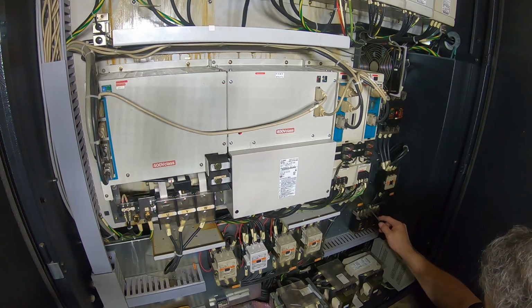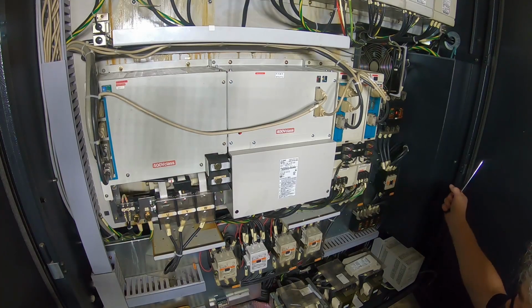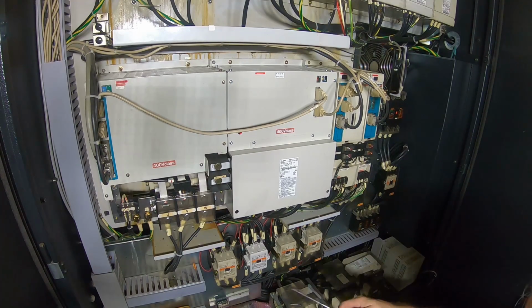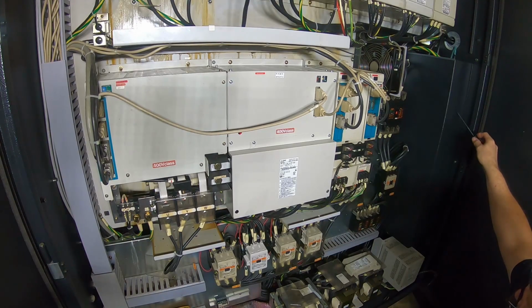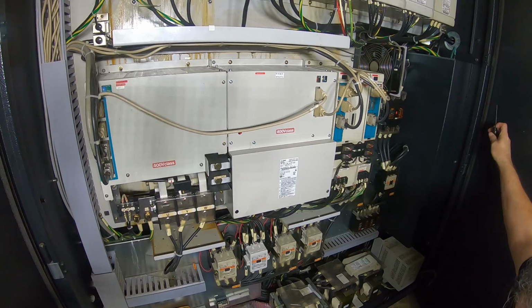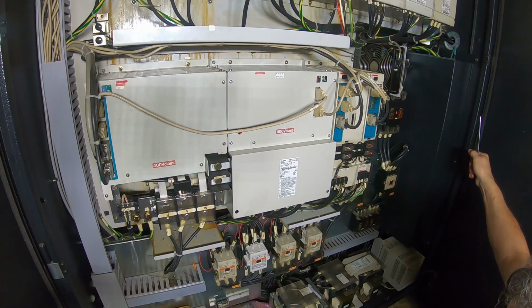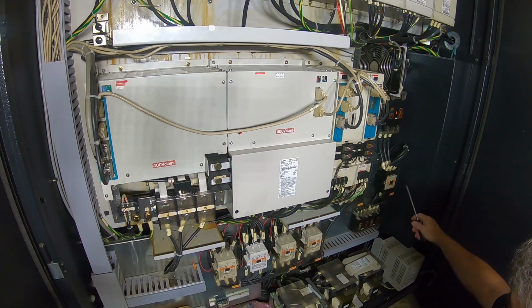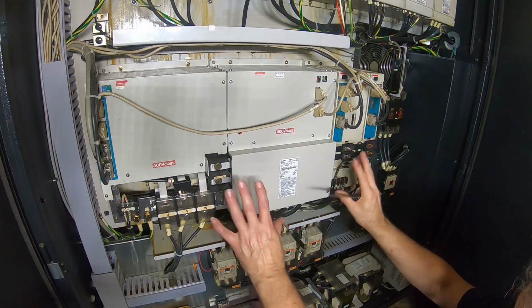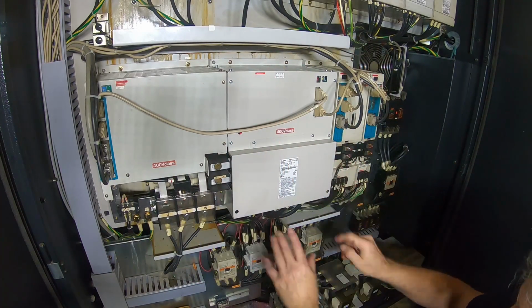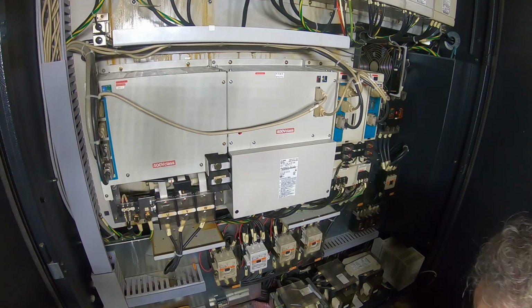Or maybe it closes immediately when you turn the main power on. Like I said, all of this is powered up even though the control is off, but if you leave the main power circuit breaker over here on the outside of the machine on, then all of this area is powered up in this cabinet continuously.